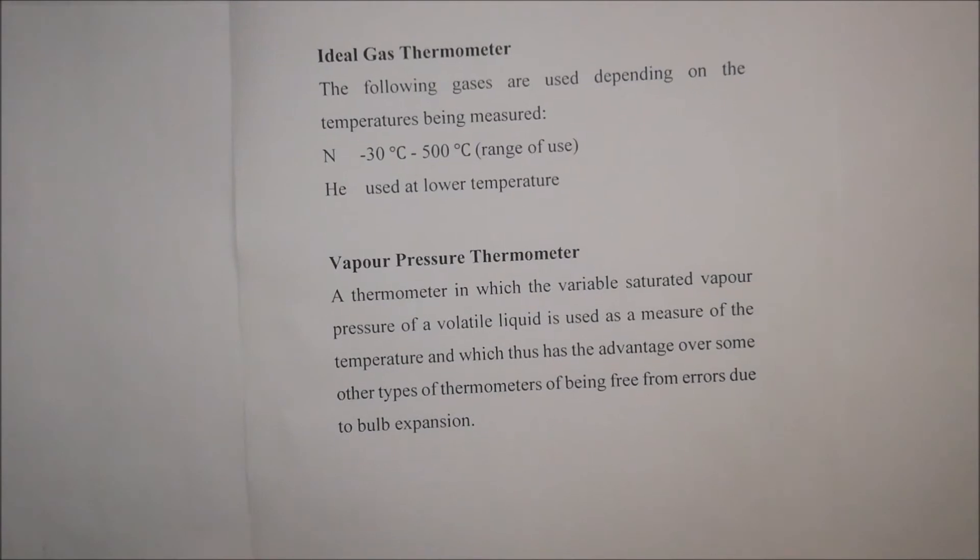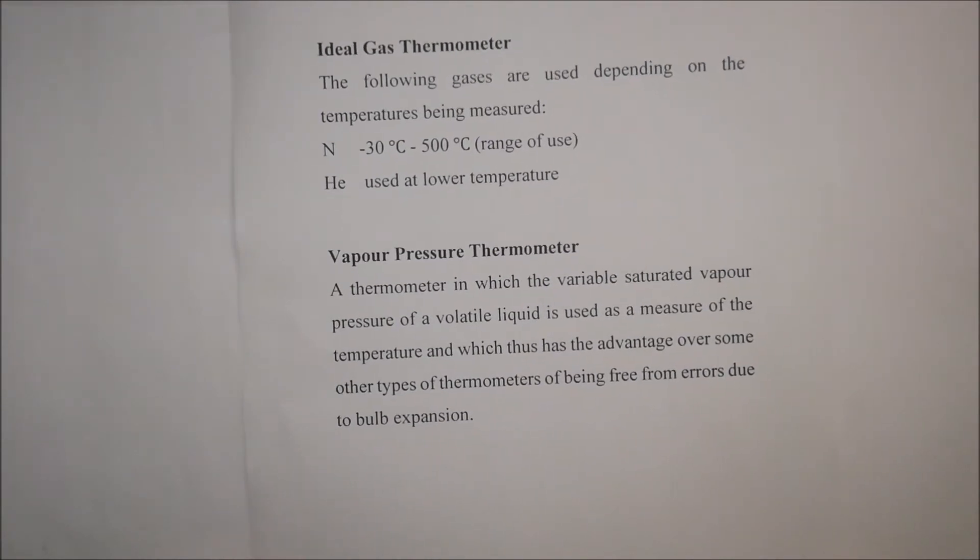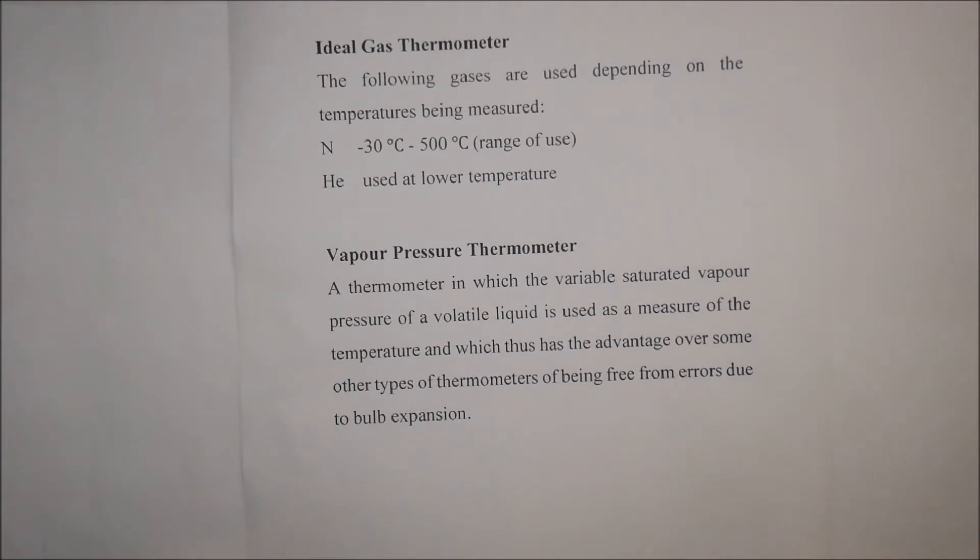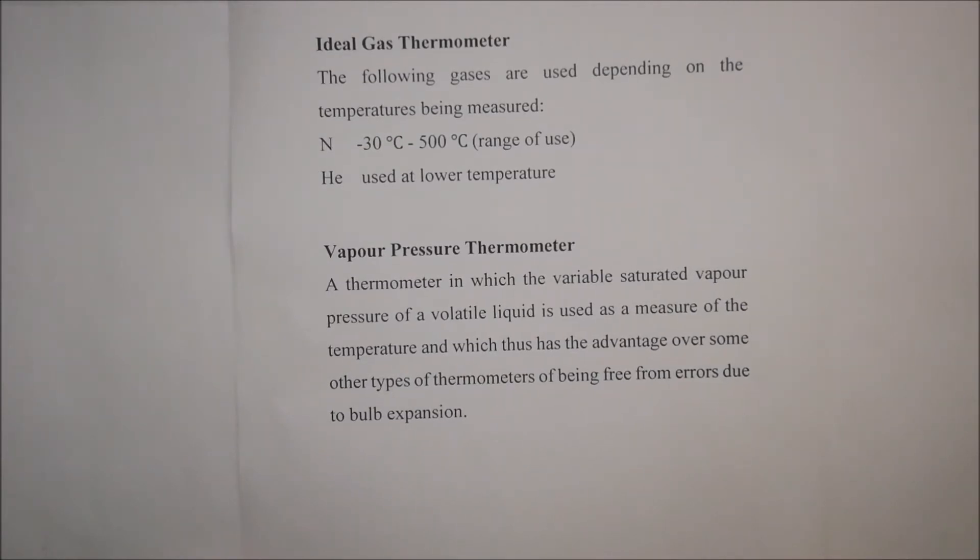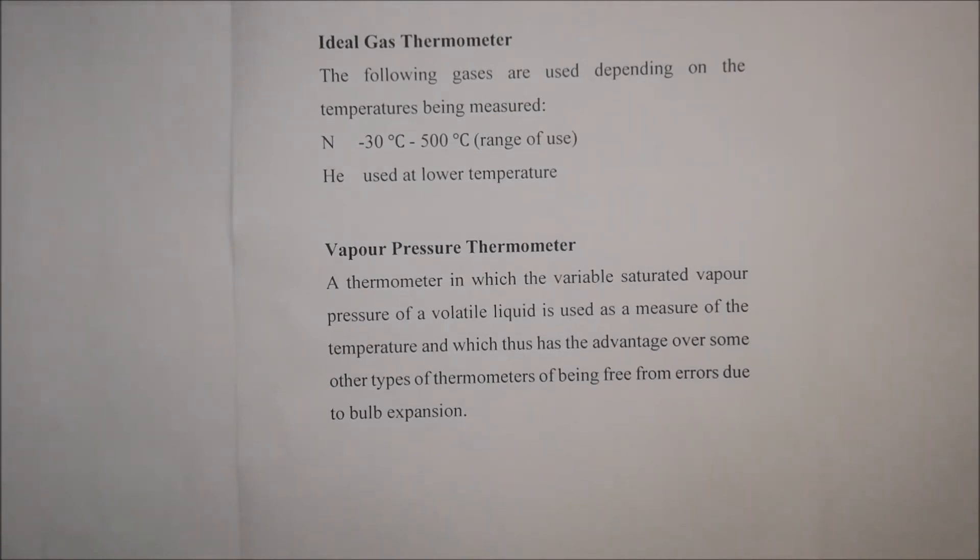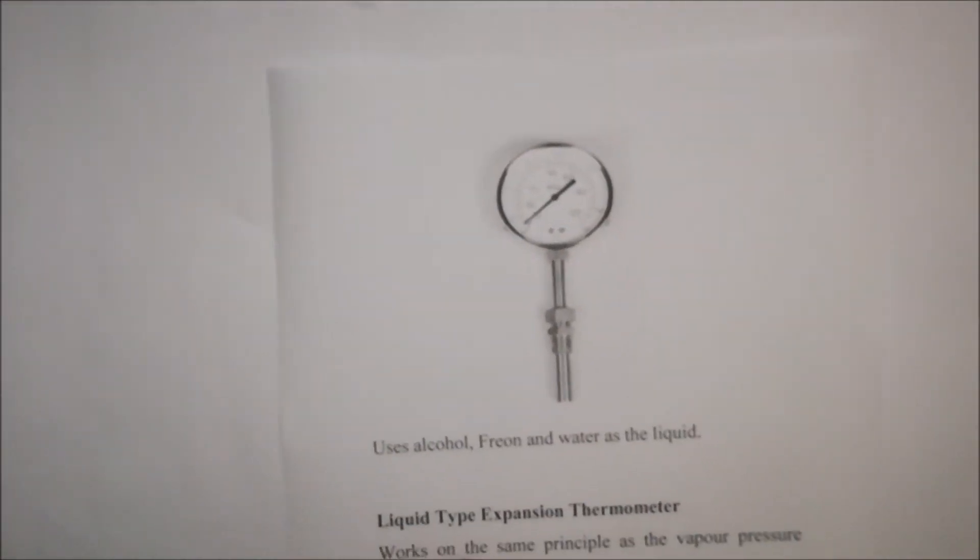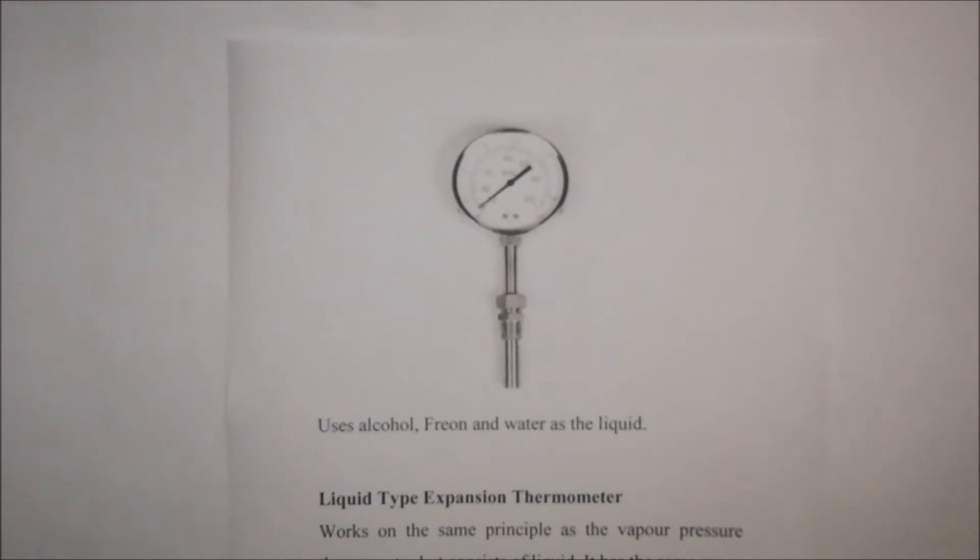You also get vapor pressure thermometers. It's a thermometer in which a variable saturated vapor pressure of a volatile liquid is used as a measure of the temperature and which thus has an advantage of being free from errors due to bulb expansion. You'll perhaps see an example of one of these. These type of analog gauges are being used to measure temperatures, and they use alcohol, freon, and water as a liquid.